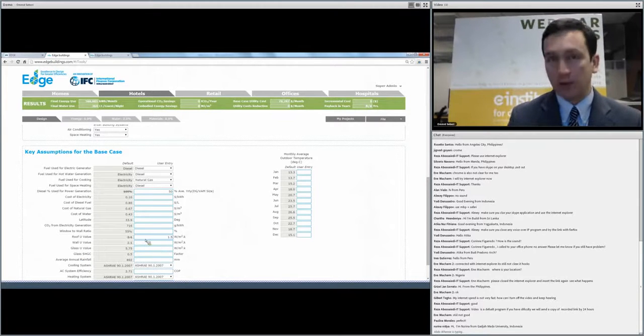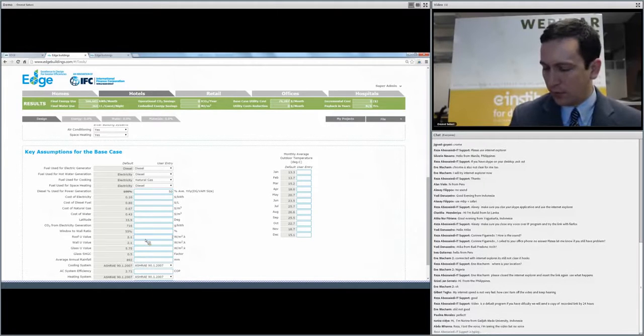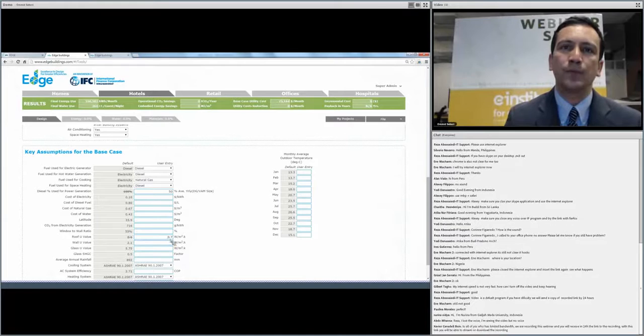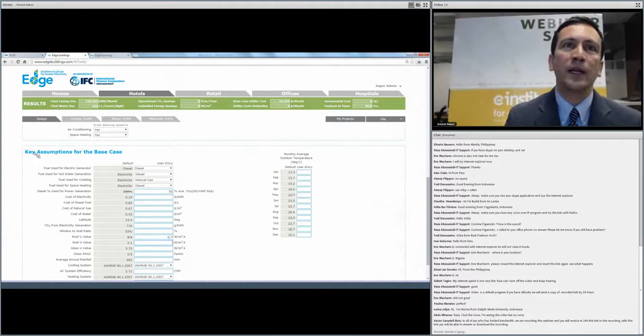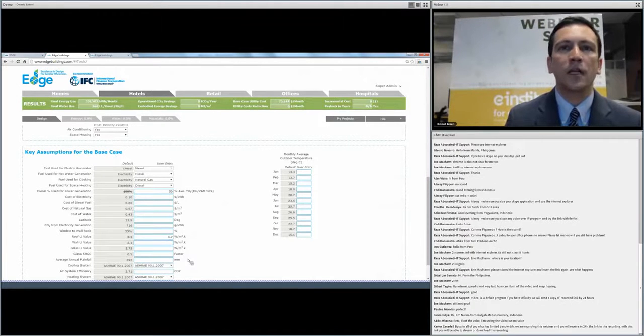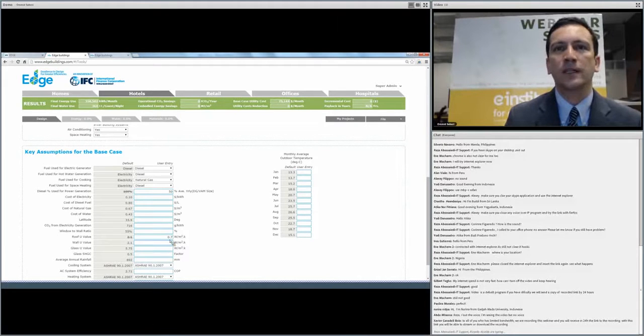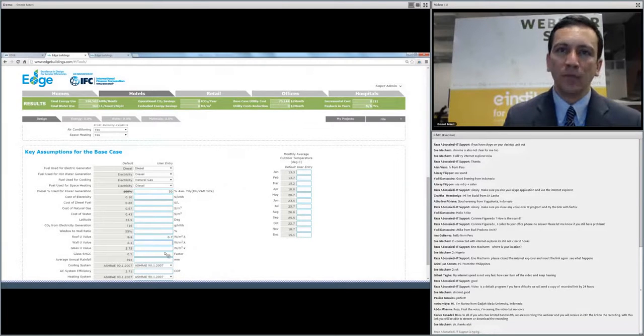they can change that here by saying that, okay, the new regulation on the roof U value is 0.7, apologies, 0.7. So then the baseline will be adjusted based on this. But remember that these are the baseline assumptions. And if one changes this, then they need to bring the facts why they have changed this. If there is a regulation, then that regulation needs to be presented to show why the baseline is changing. So this is not your building, this is the baseline building.